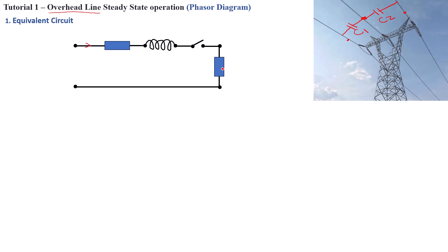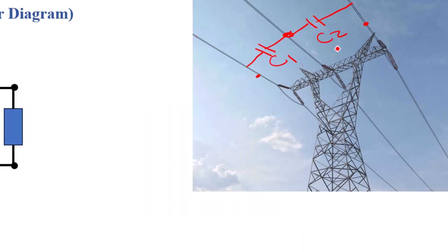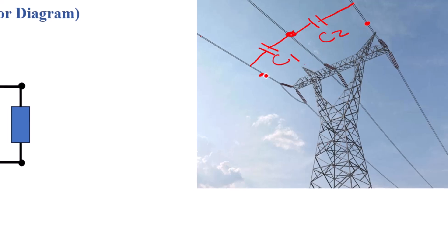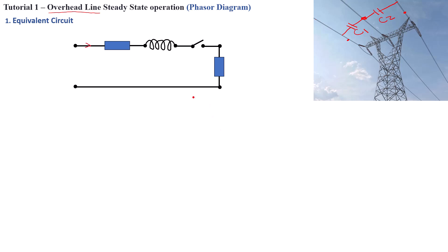Remember, this only applies to overhead transmission lines. If you are dealing with underground systems, the long, short, medium classifications do not apply there, because the cables are going to be too close to each other and you have to consider the capacitance that will build up around the bundled cables. As can be seen here on a normal overhead transmission line, the line spacing between the cables can go up to one meter. But this is not the case underground, where the cables are bundled very tightly together and the capacitance is going to be much higher.